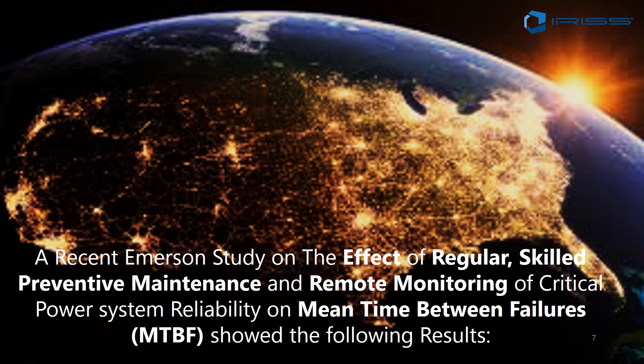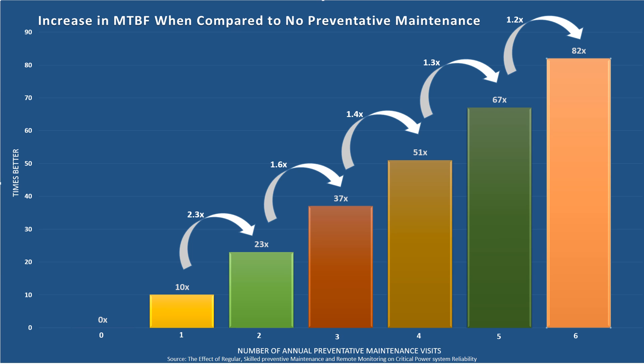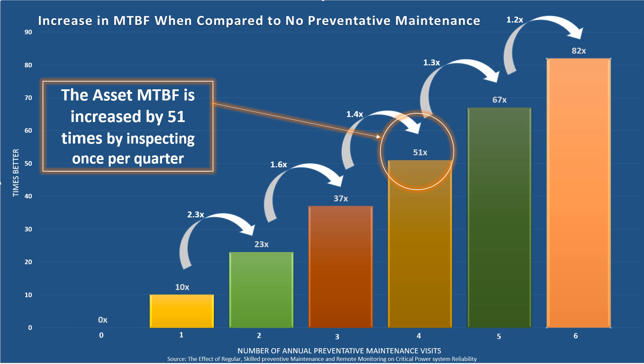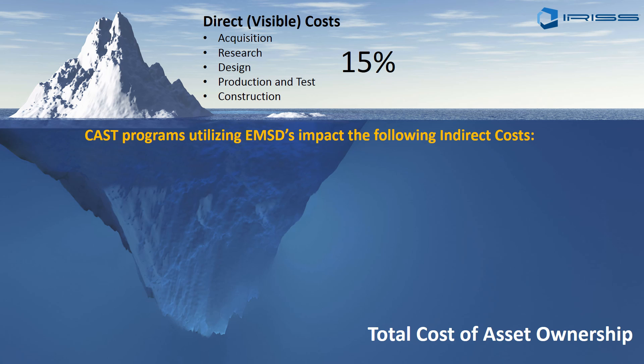Another data point comes from a report by Emerson on the effect of regular skilled preventive maintenance and remote monitoring of critical power systems on the mean time between failure, or MTBF — a key metric in reliability. What we've seen is that if we do four inspections a year, every three months — which is very simple to do with EMSDs — and we use wireless temperature monitoring such as a delta-T alert system, we can see an MTBF increase of 51 times. That is a huge metric for critical power environments such as data centers, where increasing MTBF by 51 times significantly reduces the chance of losing power or equipment.